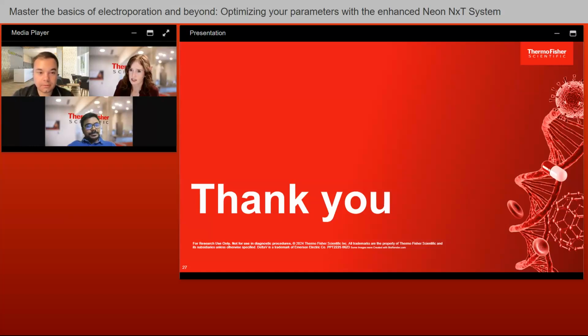And just to add to that, Shahan, sorry, Kevin, the reason why the instrument shows that error message is those extreme energies can be dangerous to cell types, to cells. And so, in order to prevent arcing from happening, we have done a lot of testing to make sure that we are within that range.